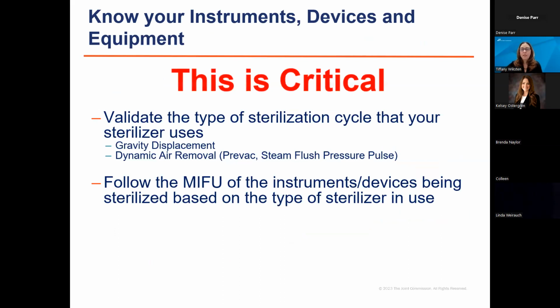Know your instruments, devices, and equipment. Typically in large central sterile locations, this isn't too big of an issue. You have a very qualified, educated staff. This is their dedicated job. They know the types of sterilizers that are in use, the sterilization cycles that are used. But sometimes in our decentralized locations that may have tabletop sterilizers where sterilization is only a fraction of the staff's responsibility, they don't always know the sterilization cycle that that sterilizer provides. And you need to know the sterilization cycle that is provided by that sterilizer so you know which set of instructions for use to follow in the instrument or device instructions for use.